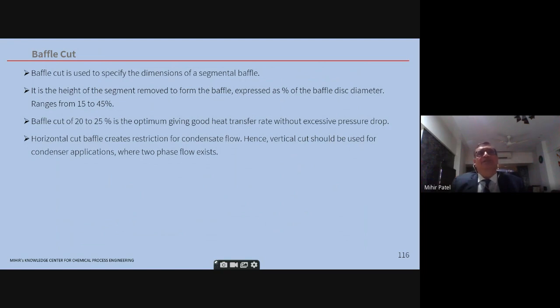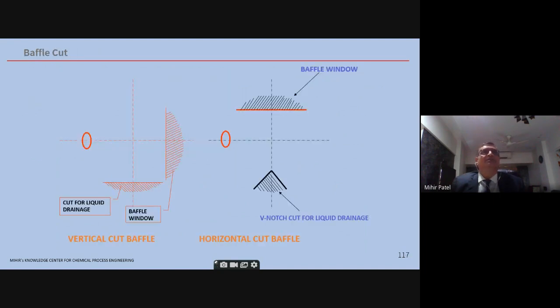Horizontal cut baffle is normally kept for single phase fluids, and for condensing phase fluids where you have two phase flow, always you keep vertical baffle cuts. So on the left you see vertical baffle cut. At the bottom is a small cut for drainage liquid. On the right hand side, horizontal baffle cut and small V notch for liquid draining.